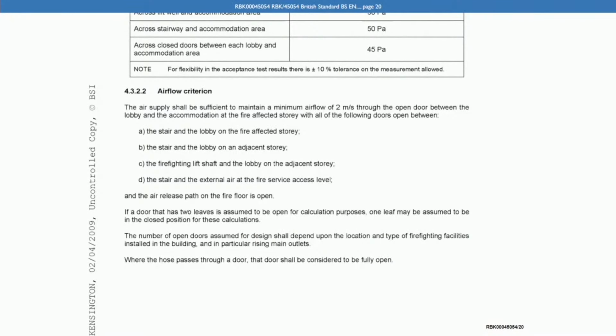4.3.2.2, we can see it says there the air supply shall be sufficient to maintain a minimum flow of 2 metres per second through the open door between the lobby and the accommodation at the fire-affected storey, with all of the following doors open between: the stair and the lobby on the fire-affected storey, the stair and the lobby on an adjacent storey, the firefighting lift shaft and the lobby on the adjacent storey, the stair and the external air at the fire service access level, and the air release path on the fire floor is open. Now, I appreciate the point you're making, I think, is that the design was only intended to ever have one door open. That's the stair door, yes?